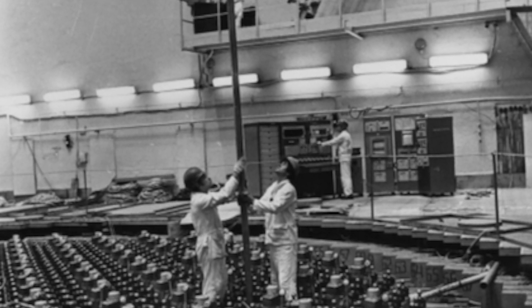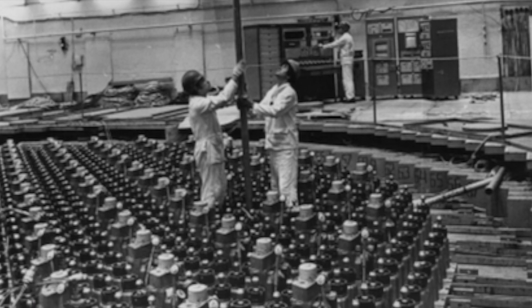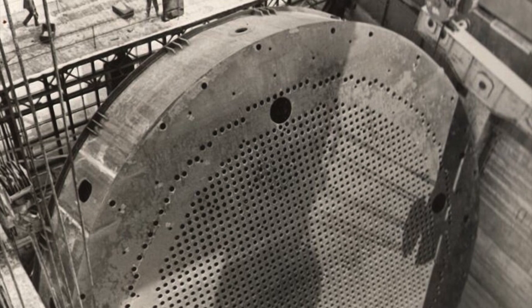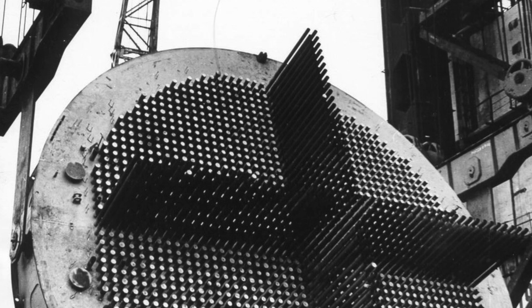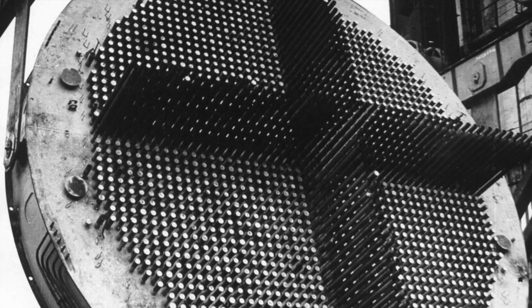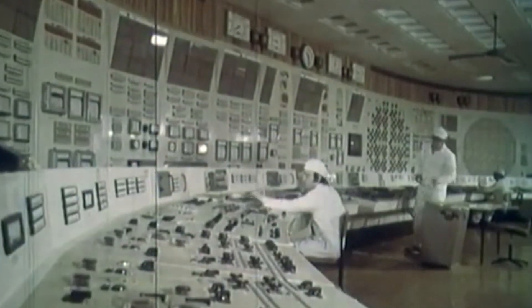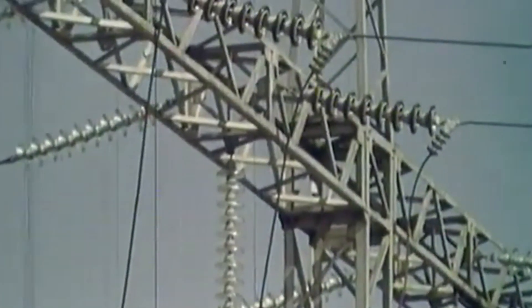The reactor installed at the 4th unit of the CHNPP was designed in the 1960s by the NIKIET (Research and Development Institute of Power Engineering) of the USSR Ministry of Medium Machine Building, and the scientific leadership was provided by the Kurchatov Institute of Nuclear Power Engineering. It was named RBMK-1000 — a high-power channel-type reactor of 1,000 electric megawatts. It uses graphite as the moderator and water as the coolant. The fuel is uranium compressed into pellets and placed in fuel elements made of uranium dioxide and zirconium shells.